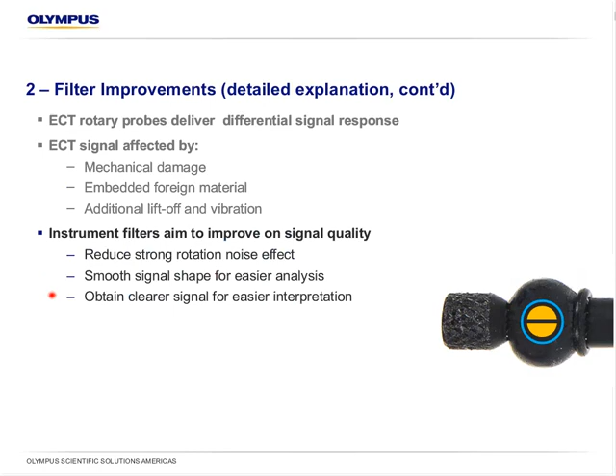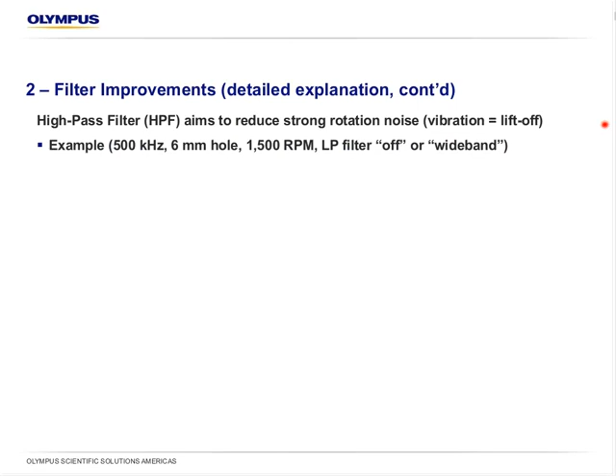So, the high pass. I told you there's a high pass and there's a low pass in the settings. The high pass is the most important. That's the filter that does most of the cleaning up of the signals, basically. The high pass filter aims to reduce strong rotation noise or vibration or liftoff. If I use this example here, imagine aluminum, it's a standard aluminum scan at 500 kilohertz. It's a 6 millimeter hole. The speed of the scanner is 1500 RPM. The low pass is off or wideband because a low pass can never be totally off.